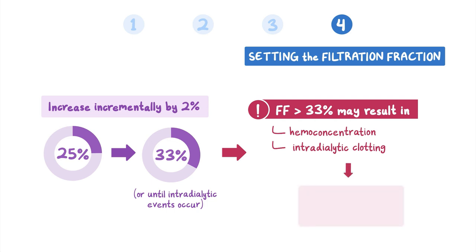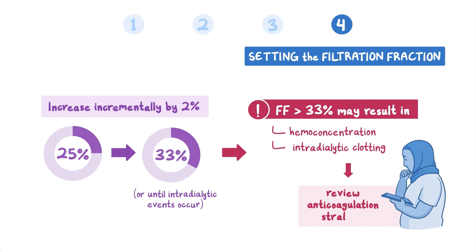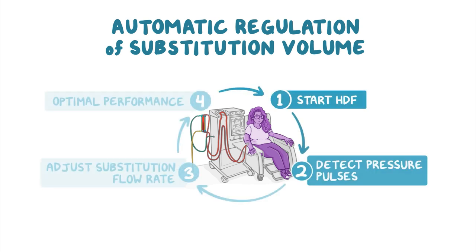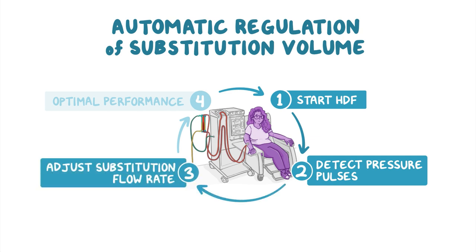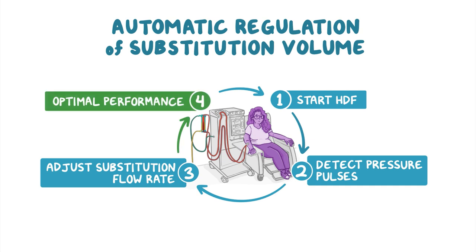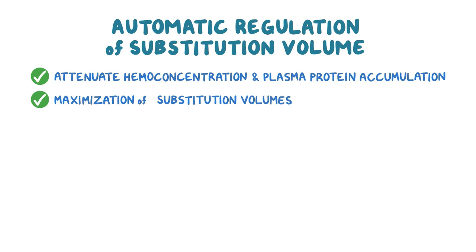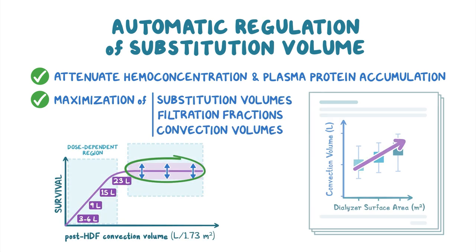Intradialytic clotting complications may require the physician to review the anticoagulation strategy. Patient-specific optimization can be refined further with automatic regulation of substitution volume, which is a feature available on some dialysis machines. Such features detect pressure changes in the extracorporeal circuit and adjust substitution flow rates accordingly in real time to optimize performance and outcomes, helping to attenuate hemoconcentration and plasma protein accumulation, allowing for maximization of substitution volumes, filtration fractions, and convection volumes for each patient.